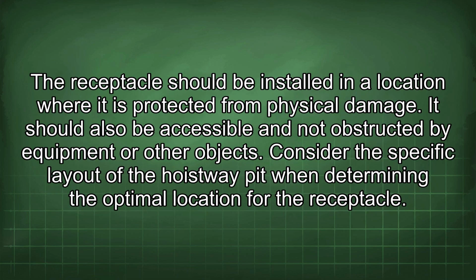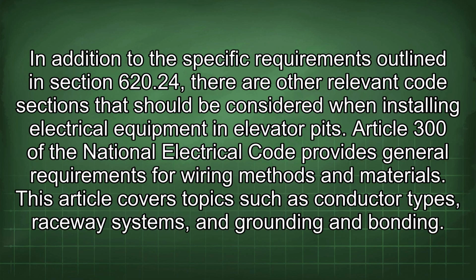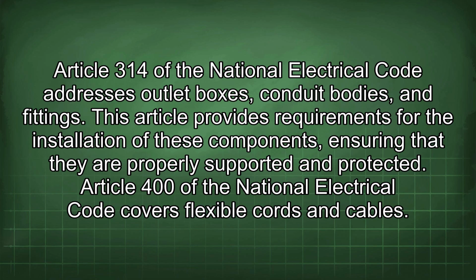The receptacle should be installed in a location where it is protected from physical damage. It should also be accessible and not obstructed by equipment or other objects. Consider the specific layout of the hoistway pit when determining the optimal location for the receptacle. In addition to the specific requirements outlined in section 620.24, there are other relevant code sections that should be considered when installing electrical equipment in elevator pits. Article 300 of the National Electrical Code provides general requirements for wiring methods and materials. This article covers topics such as conductor types, raceway systems, and grounding and bonding. Article 314 of the National Electrical Code addresses outlet boxes, conduit bodies, and fittings.